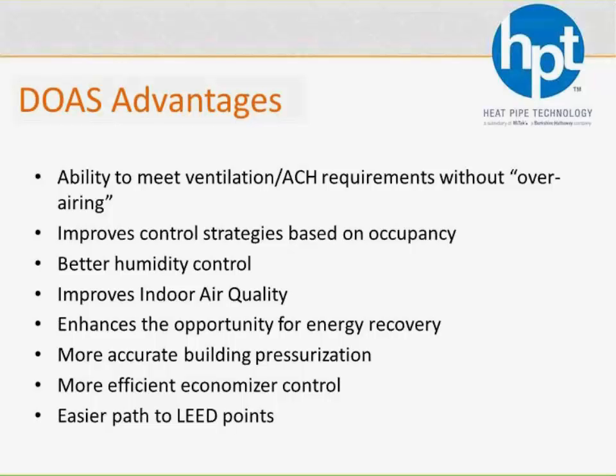It does enhance the opportunity for energy recovery if you're bringing all the outside air to a single point. It makes that a lot easier, gives you a lot better options. And it also gives you more accurate building pressurization. Again, it's all in one place and more accurately measuring what's coming in versus what's coming out. And you do get more efficient economizer control. Again, if you're able to use that outside air for economizer mode and it's all right there in one source instead of mixing, it makes it a lot easier and a lot more efficient to control that. And oftentimes when it comes to LEED, you do find that there's an easier path to get more points simply by decoupling that system.